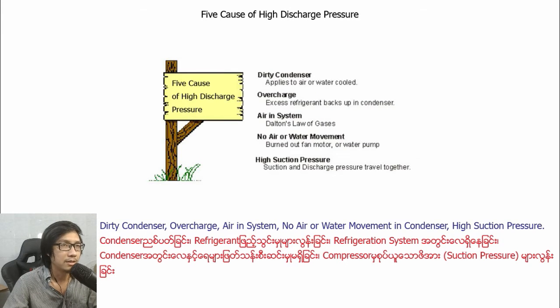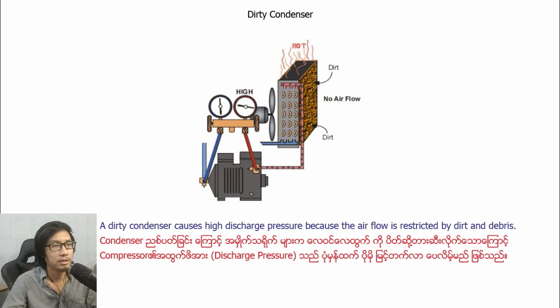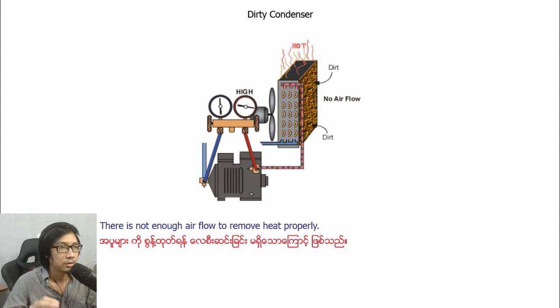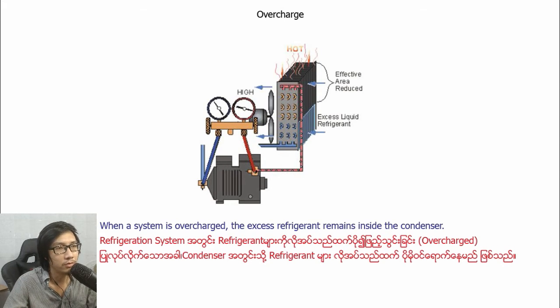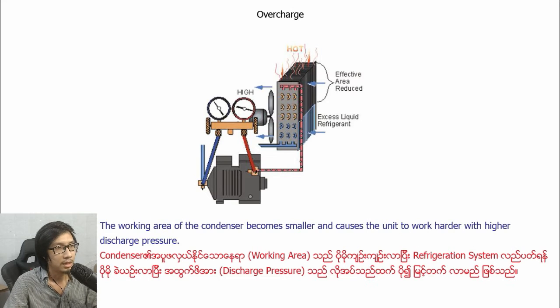Five causes of high discharge pressure: dirty condenser, overcharge, air in system, no air or water movement in condenser, high suction pressure. Dirty condenser. A dirty condenser causes high discharge pressure because the airflow is restricted by dirt and debris. There is not enough airflow to remove heat properly. When a system is overcharged, the excess refrigerant remains inside the condenser. The working area of the condenser becomes smaller and causes the unit to work harder with higher discharge pressure.